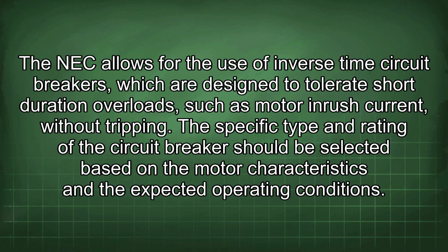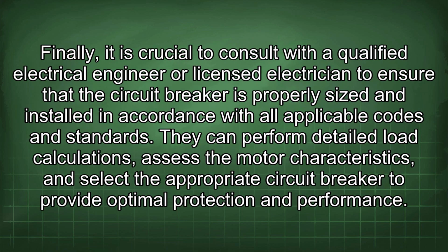The NEC allows for the use of inverse time circuit breakers, which are designed to tolerate short duration overloads, such as motor inrush current, without tripping. The specific type and rating of the circuit breaker should be selected based on the motor characteristics and the expected operating conditions. Finally, it is crucial to consult with a qualified electrical engineer or licensed electrician to ensure that the circuit breaker is properly sized and installed in accordance with all applicable codes and standards.